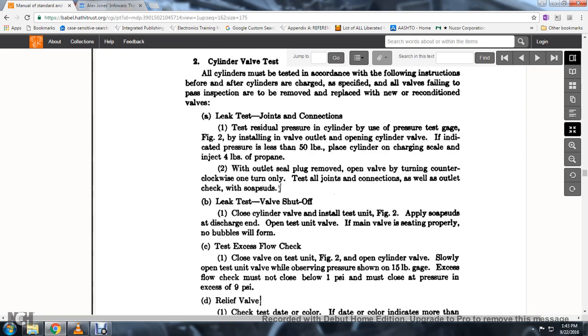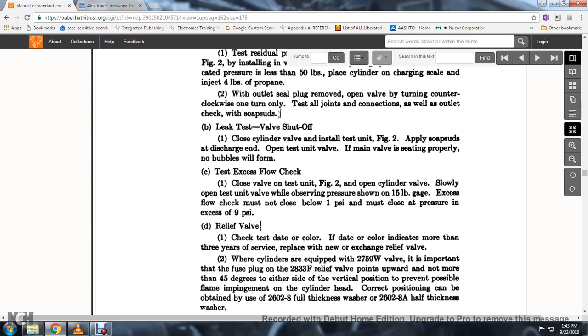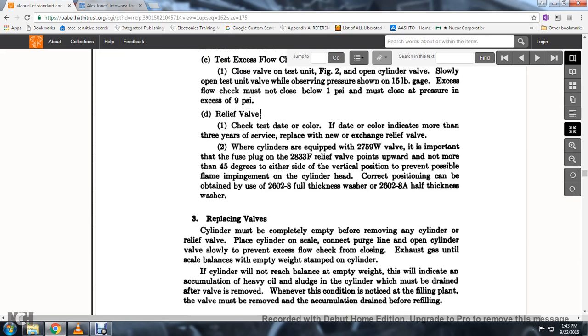Leak test with the valve shut off: close the cylinder valve, install the test unit figure 2, apply soap suds, and open the test unit valve; if the main valve is seating properly, no bubbles will form. To test the excess flow check: open the cylinder valve slowly, then open the test valve while observing the pressure on the 15-pound gauge; the excess flow check must not close at a pressure below 1 PSI, and must close at a pressure in excess of 9 PSI.